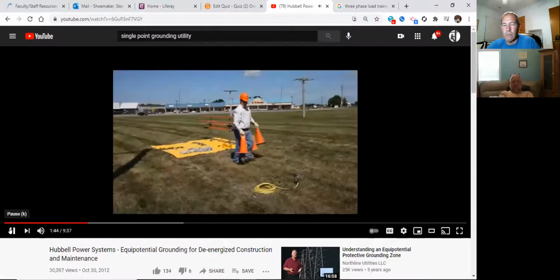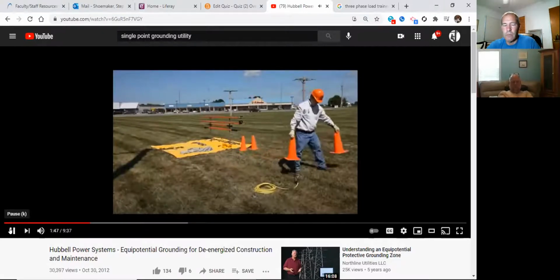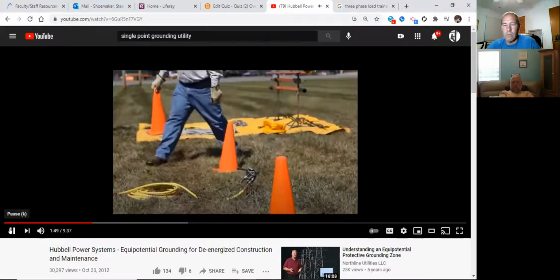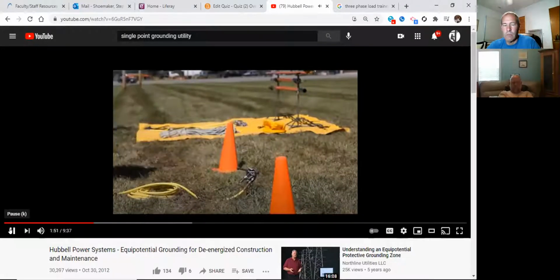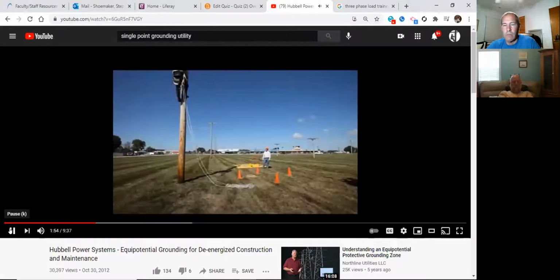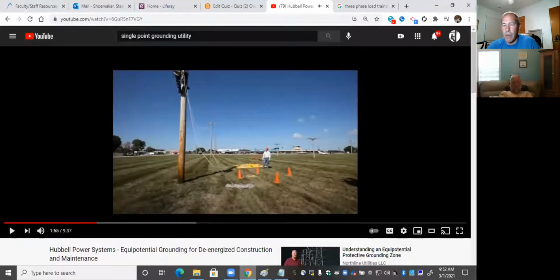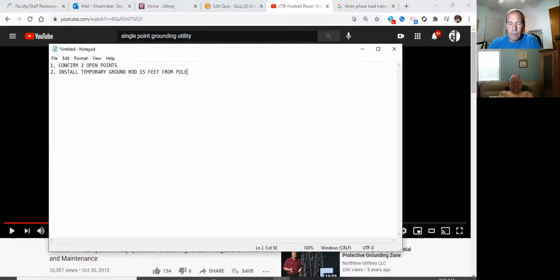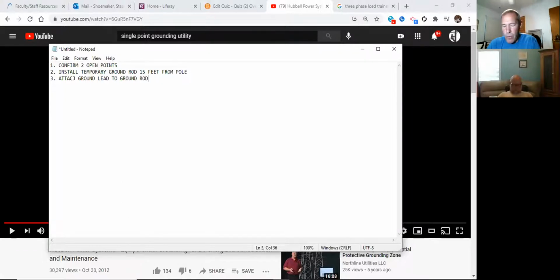Next, the groundman places safety cones around the ground rod as a warning barrier for other workers and the public. Next, he uncoils the grounding set attached to the rod and prepares to set up the clamp on the free end of the cable. Okay, so we're going to go to step 3. Attach ground clamp lead to ground rod. And very important here, what else did he do? What else did he say? Put the safety cones out.